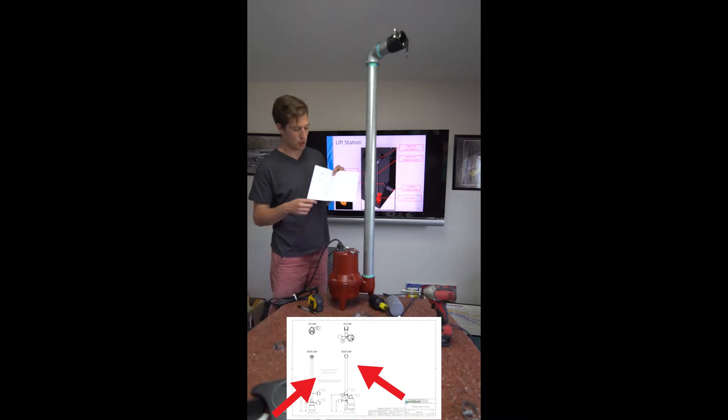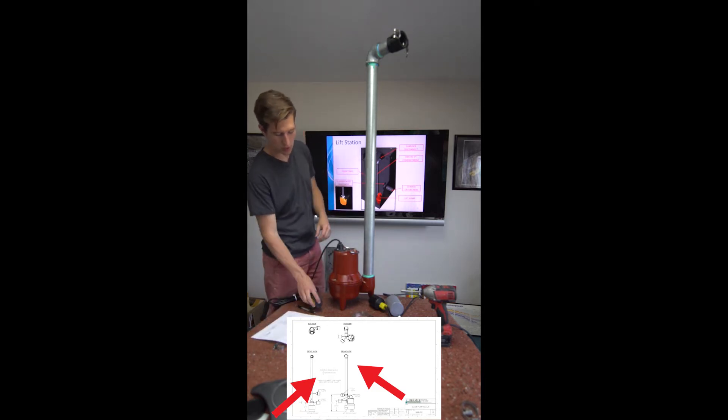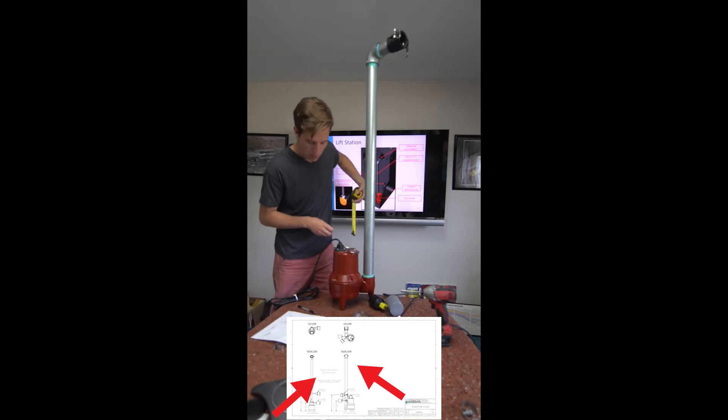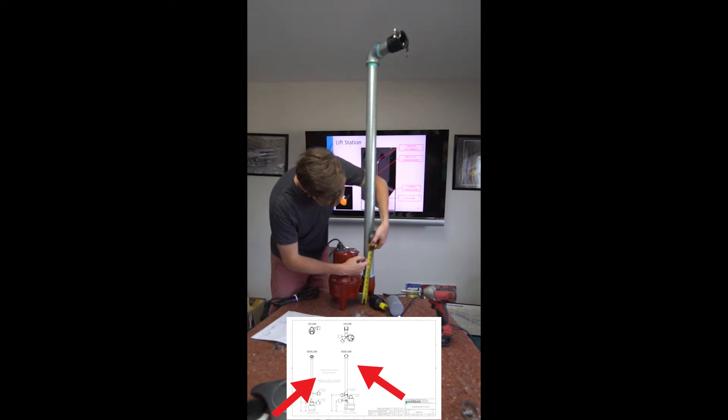First thing we want to do is make marks where our pump floats are going to be. It is important to measure from the bottom of the pump. So I'm going to take my tape measure. First one is at 10 and a half inches. Measure from the bottom. 10 and a half. Make a line.